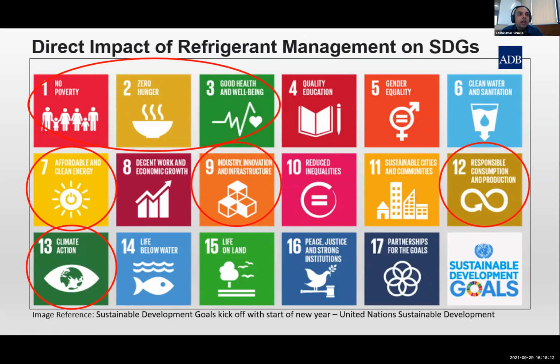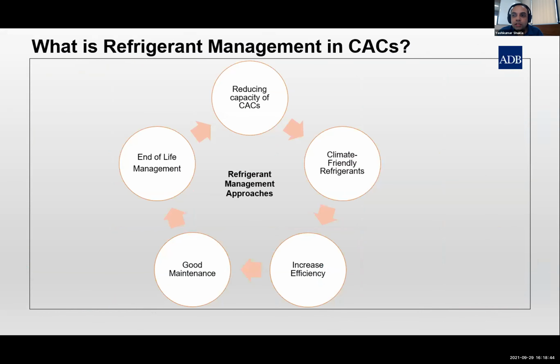If you look further, out of the 17 SDGs, Sustainable Development Goals, that have been proposed by the UN, you can see that refrigerant management would impact almost 7 of those directly, and there will be many indirect impacts as well. So what is refrigerant management in centralized air conditioning systems? I've broken it down into 5 simple steps. The first step is you have to reduce the capacity of the centralized air conditioning system. By designing our buildings in a way that reduces the cooling and heating capacity, you reduce the refrigerant use in the centralized air conditioning system. That's the first step to reduce the use of refrigerants.